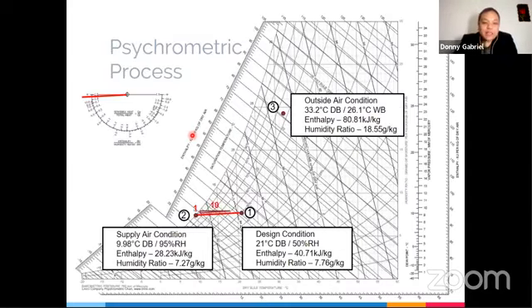Okay, on our psychrometric process, from outdoor air, it doesn't go this way. It doesn't go from 3 to 1. It goes here first, 100% saturation, and then it goes here until it reaches this point. So every time air comes out from the coil, and you can see there's a condensation taking part, it's 100% saturated with moisture before it goes to our room. So this is important, no? It's important to always know that the air coming from the coil is always at saturation point. Okay, that's important. The air coming from the cooling coil is always at saturation point.